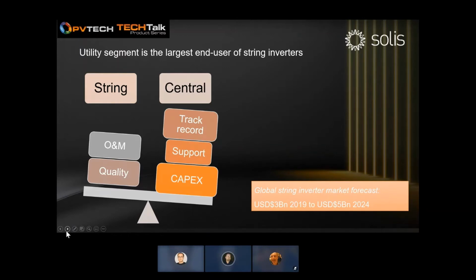If someone is interested, I think we can share the summary of the DNV report we just mentioned before, that not only praises the track record, but also states that the life projection of our inverters exceeds market standards. But as I was saying, if a string inverter fails, you just swap it for another one and send the defective one to us for repair. The downtime of that inverter, and therefore the loss of production of those 255 kilowatt, against whatever you have on your central inverter, if that one stops working, the loss of production of that inverter will be reduced to whatever time your O&M team requires to perform that swap.